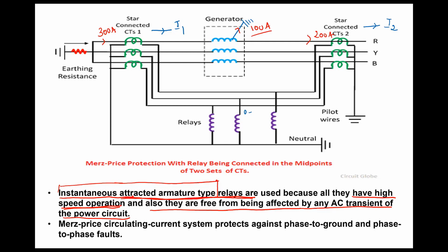We have already seen that the merz-price circulating current scheme, or differential current scheme, protects against phase to ground faults and phase to phase faults in the stator winding.